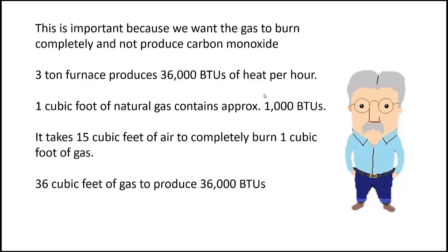So we need 36 cubic feet of gas to produce 36,000 BTUs. We're going to multiply 36 times 15. That's 36 cubic feet of gas times 15 cubic feet of air. And that equals 540 cubic feet of air that that draft inducer fan has to blow through that furnace every hour to completely burn the natural gas.